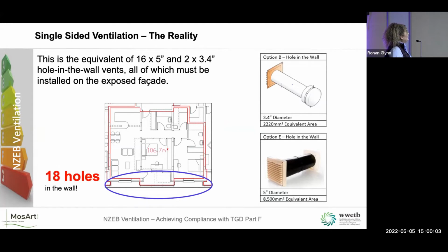Here you can see there's a window there, three windows here, another window there. There's not even wall space to put background ventilators in. If you have to double up that requirement, you're talking about structural issues as well. So it's really impractical to have natural ventilation if it's single-sided. It's very, very difficult. The solution the client eventually went with was CMEV, because with CMEV you can reduce the amount of holes in the walls.